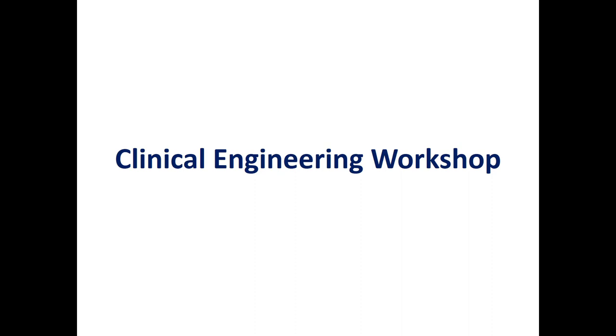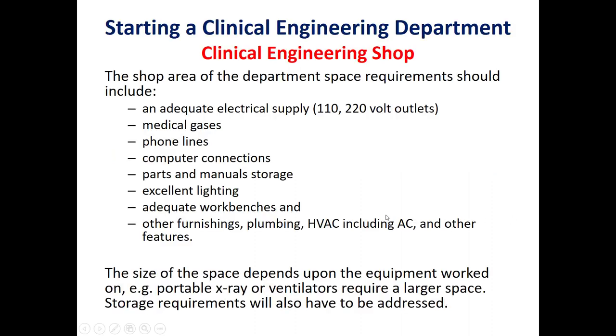Now we will move to the last point in Part 2, which is about the clinical engineering workshop. The shop area space requirements should include adequate electrical supply, medical gases for testing ventilators and anesthesia machines, phone lines, computer connections integrated into the hospital system, parts and manual storage area, excellent lighting, and adequate workbenches. The size of the space will depend on the size of the equipment to be repaired, fixed, or calibrated — for example, portable X-ray machines or ventilators require a larger space.